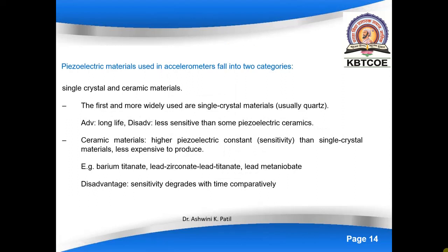The piezoelectric materials used in accelerometers fall in two categories: single crystal and ceramic materials. The most widely used are single crystal materials, and we must have heard about the quartz crystal. Quartz crystals are single crystals and are widely used. The advantage is long life, and the disadvantage is they are less sensitive than some piezoelectric ceramics. These are naturally occurring crystals, and so they are less sensitive as compared to ceramic material.